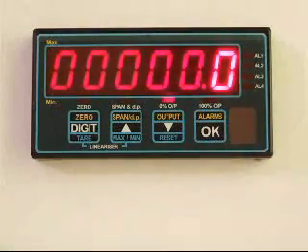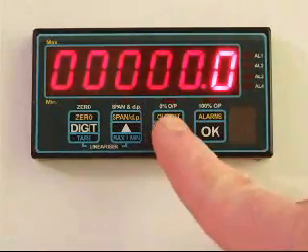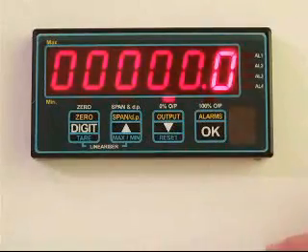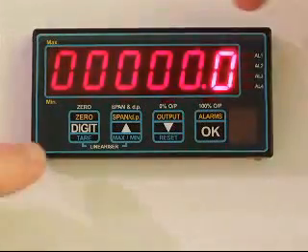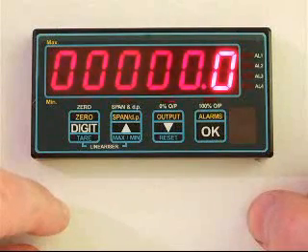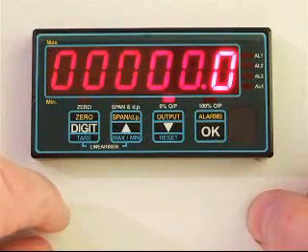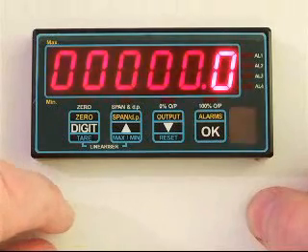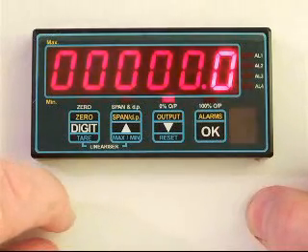And the meter came up with a prompt output low, and you'll see also we have the zero percent output LED flashing. Now the reading that we have on the display at the moment is the value that will create four milliamps output. So this is the measurement value that will create four milliamps output.